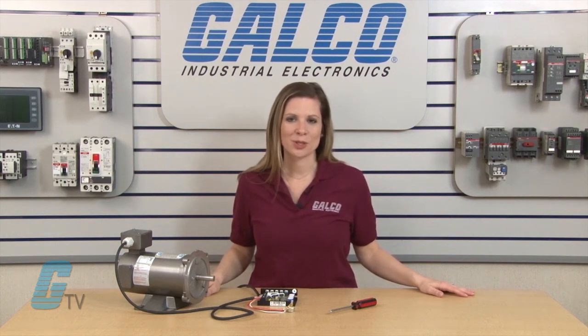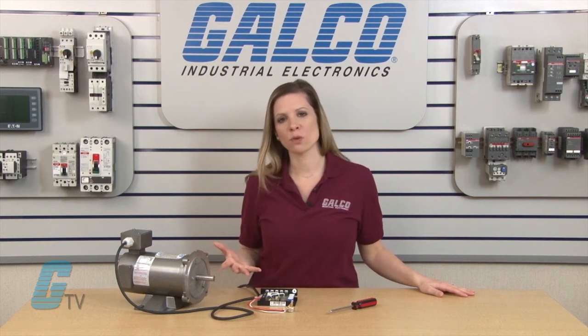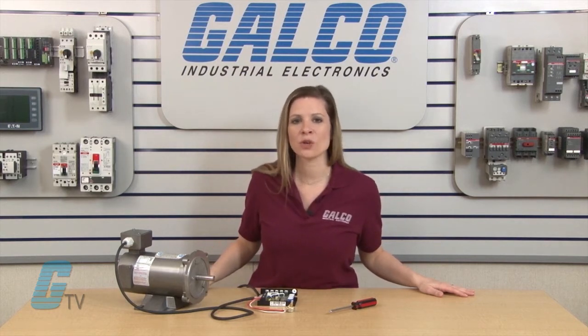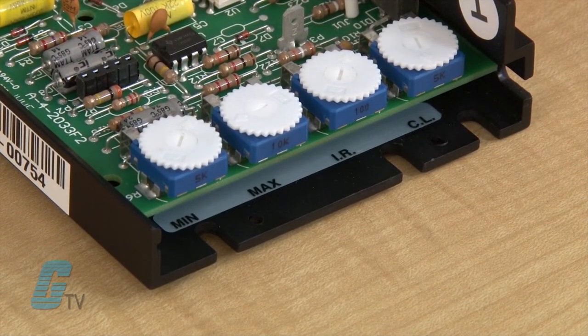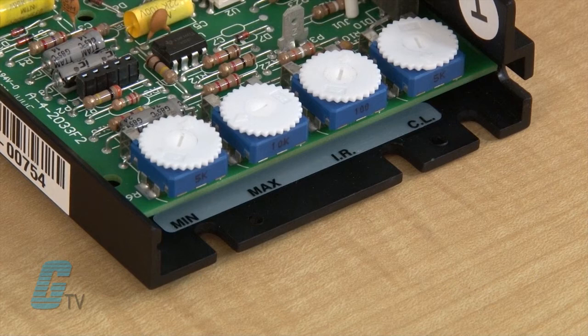This controls the armature speed by changing the armature voltage to compensate for increased or decreased motor load. The current limit trim pot provides protection from excessive armature current by limiting the maximum armature current the control can provide. This enables adjustment of the maximum torque the motor can deliver.